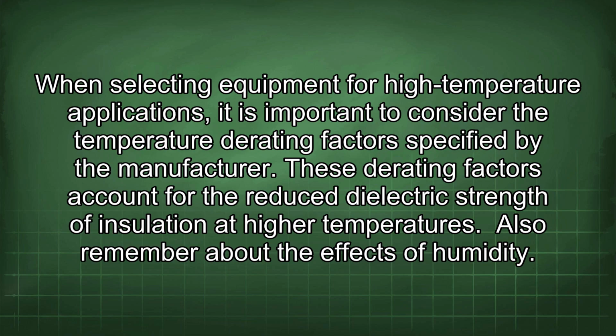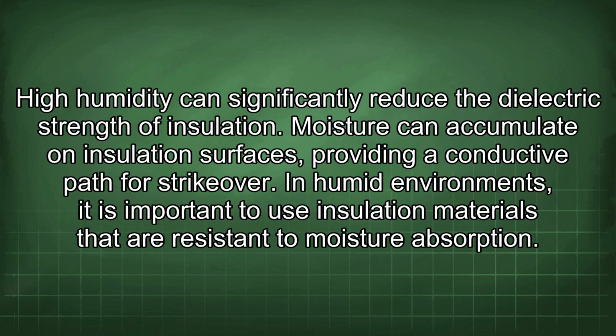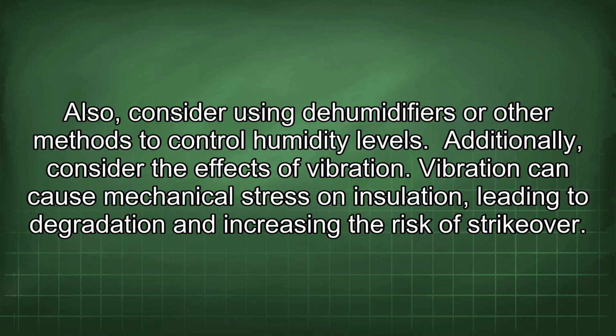Also remember about the effects of humidity. High humidity can significantly reduce the dielectric strength of insulation. Moisture can accumulate on insulation surfaces, providing a conductive path for strikeover. In humid environments, it is important to use insulation materials that are resistant to moisture absorption. Also, consider using dehumidifiers or other methods to control humidity levels.